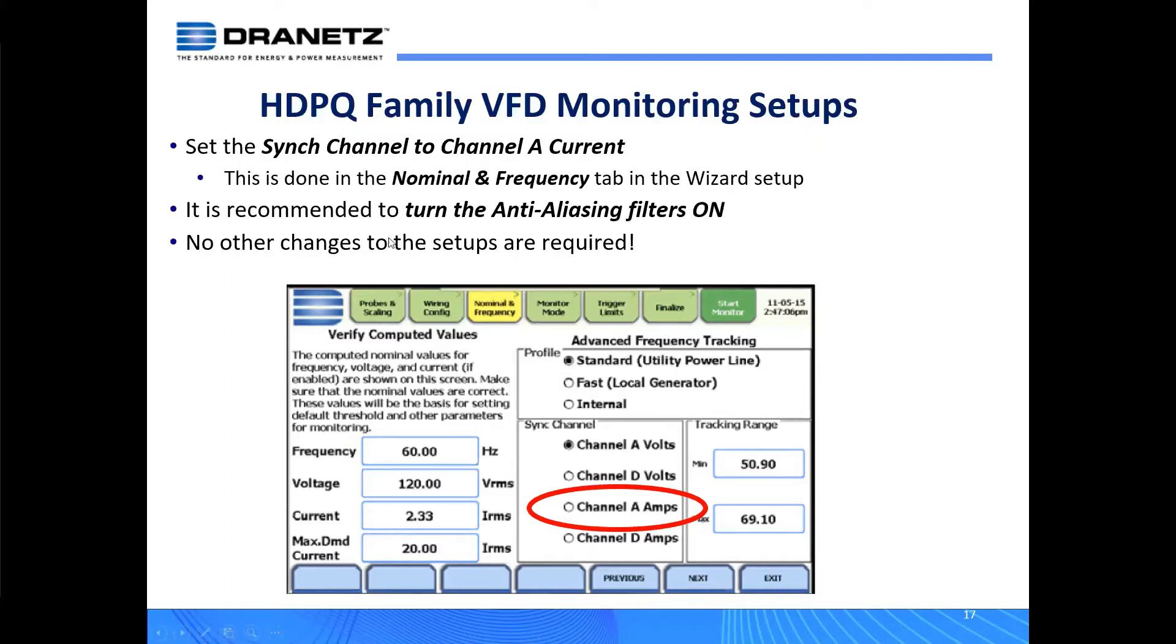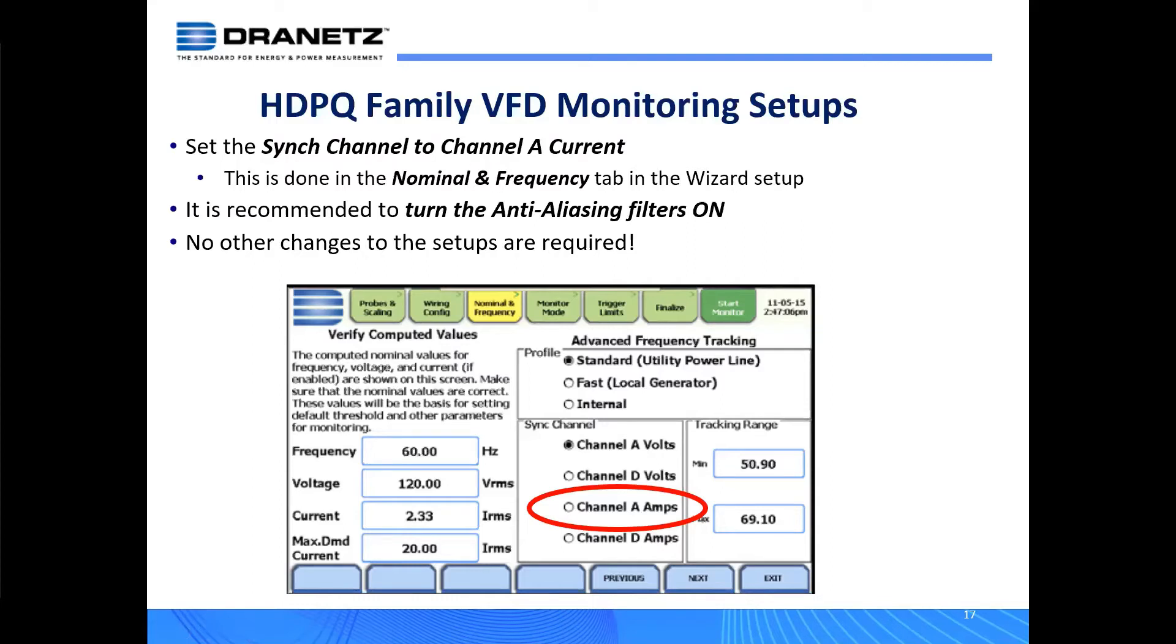It's also recommended to turn on the anti-aliasing filters. This filters out a lot of the switching noise from the VFDs because it's high speed switching and pulse width modulation on that voltage. This will filter out the majority of that noise and prevent a lot of triggering that you may not want in your measurements.